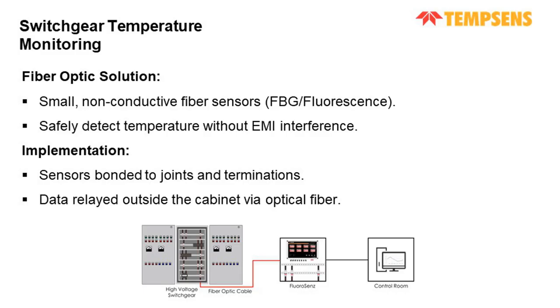So the fiber optic solution is installing a fluorescence-based system or a DTS, that is, an FBG-based system. And fiber optic sensors, being dielectric and compact, can be installed at critical junctions to provide continuous real-time temperature monitoring. And these sensors don't interfere with the electrical field and are resistant to EMI. By detecting abnormal temperature rise early, operators can take corrective action, reducing unplanned outages and improving operational safety. And fluorescence or FBG temperature monitoring systems conduct real-time monitoring to accurately measure temperature at switchgear contact points and cable joints, which makes them ideal for maintenance at unmanned substations.